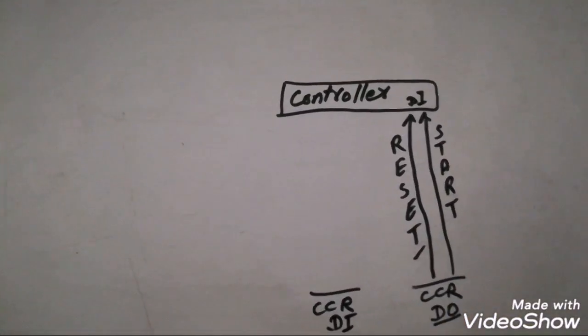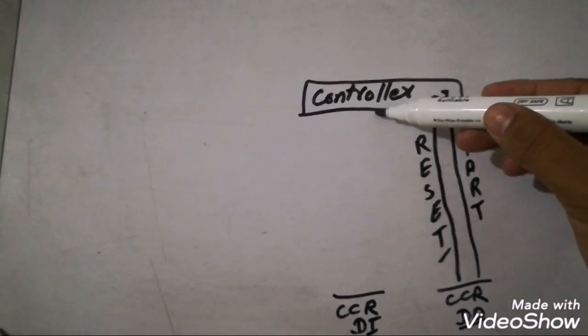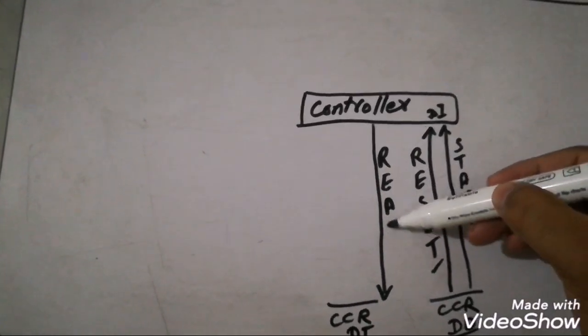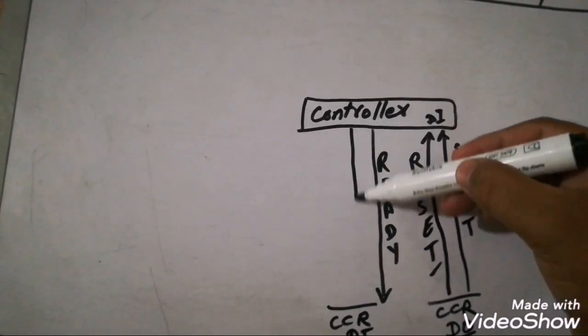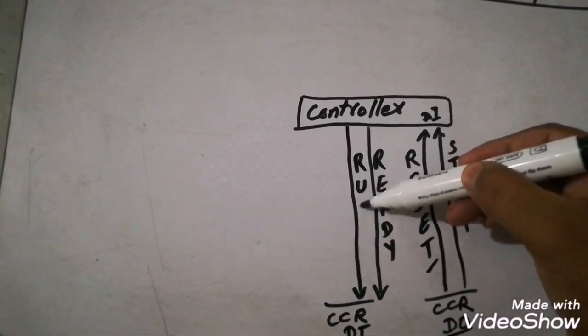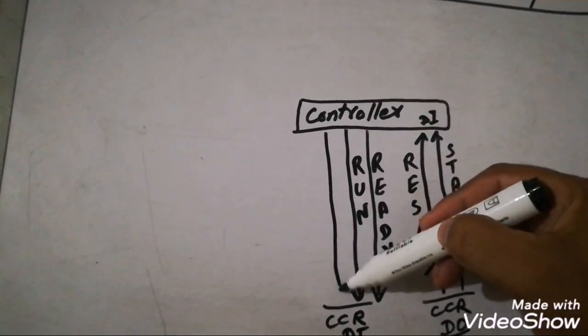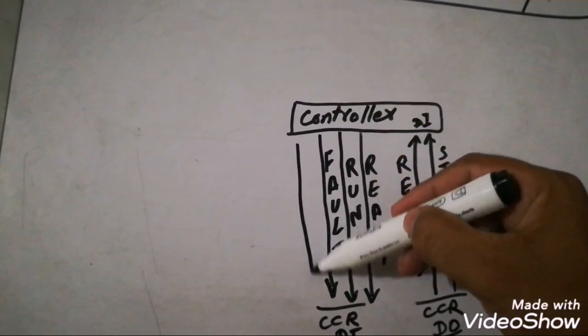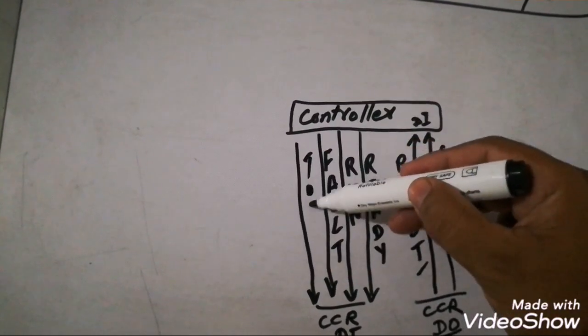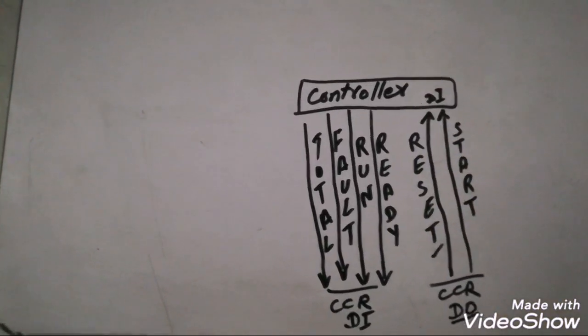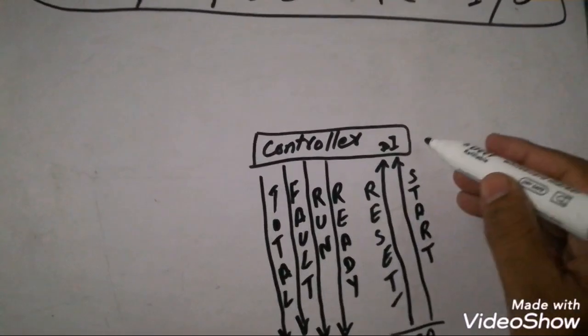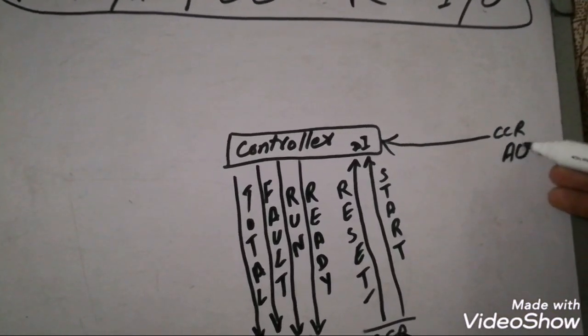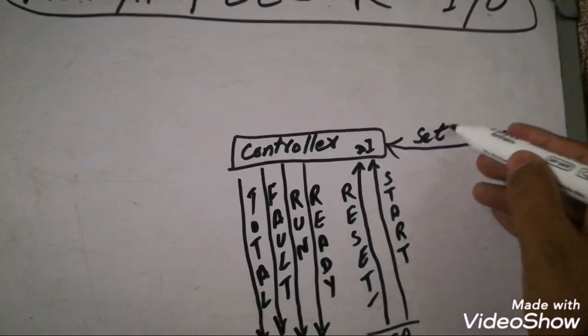The CCR digital inputs from the controller include: a ready signal indicating everything is okay and the weigh feeder is ready; a run feedback to show the operator the weigh feeder is running; a fault digital output generated by the controller in case of any fault; and a totalizer pulse — for each ton or kg as per configuration, the controller generates a pulse to show one ton has passed.